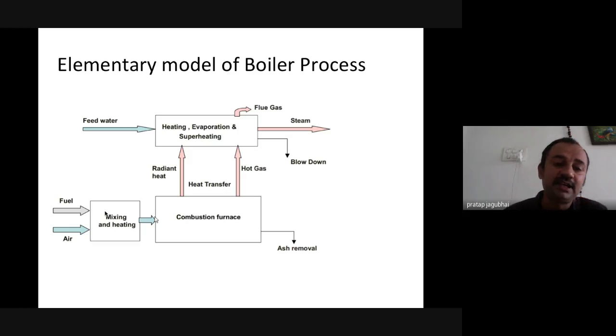So you can see in the boiler, the water cycle, which is carrying the steam drum, water tube, or water wall membrane, or a combination of all of them. And the fuel cycle, as I said, is fuel, air, smoke path, smoke tube, and the chimney. The purpose of the fuel, the furnace and the smoke path: first of all, the furnace is delivering the radiation, where the fuel and air is getting burned.